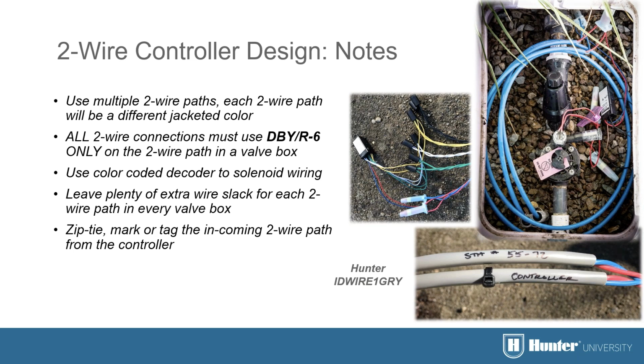As I was talking about earlier, plan packages keep changing and evolve over time, and we learn best practices from some failures. So we've compiled about 17 or 18 points now on our two-wire controller list to ensure it's being installed properly, clean, and concise. That way, if any troubleshooting is necessary out in the field, it's easily noted on the plan and you can find your way back to it. So it's really about identification, color coding, and just being super organized. Think of it like a file cabinet—if you have good folders labeled properly, everything's easy to find and troubleshoot.